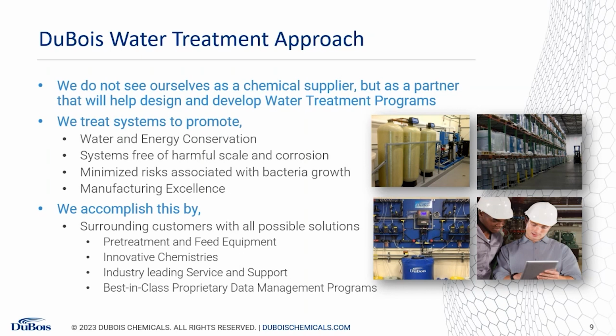This helps and can help save water in several ways. Let's say we have a product and we can run water at 500 alkalinity and 1,000 hardness, and that uses up so much water doing that. But in the past, we might run that at less than its capability - let's say 350 alkalinity and 700 hardness - because you had to build in that forgiveness in case something went wrong with the system when you didn't have eyes on it.